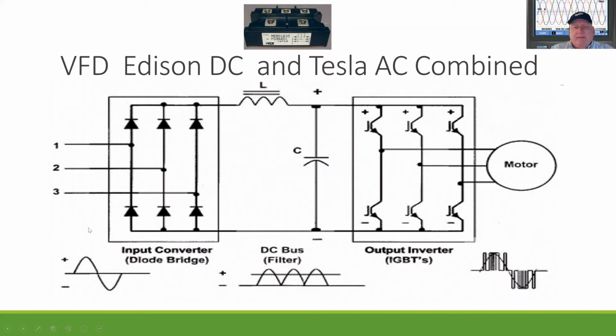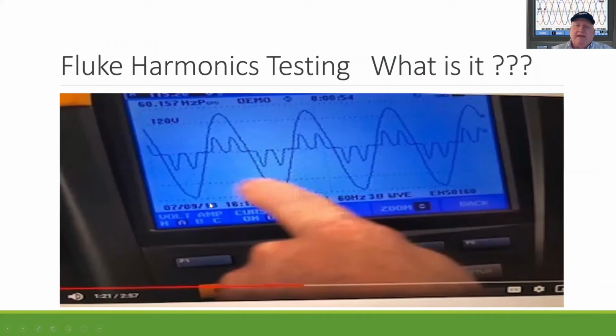Well, the issue is that the power, the current draw, ends up getting little dips in it. Here, here, here. And that's exactly what the harmonics are. The way they build radios and create frequency is basically alternating various frequencies that are sending out small amounts of power, and it'll actually radiate into the world. So as it's pulling that power, positive to negative, negative to positive, it's actually drawing the power in current. And so the current, which is the flow of the power, dependent on the load of that pump motor in general, will start showing these ripples.